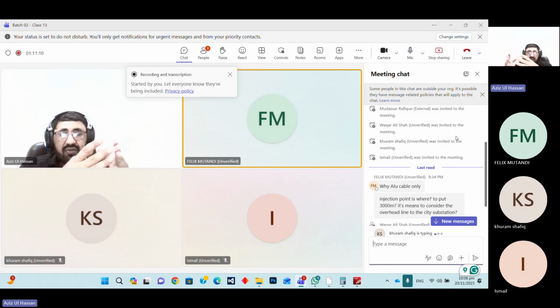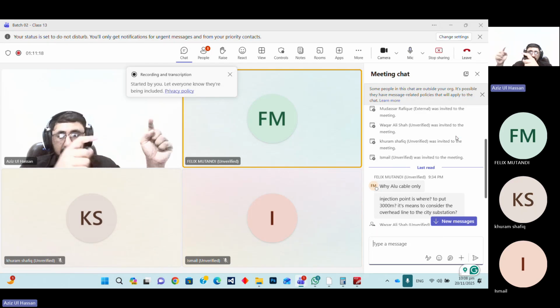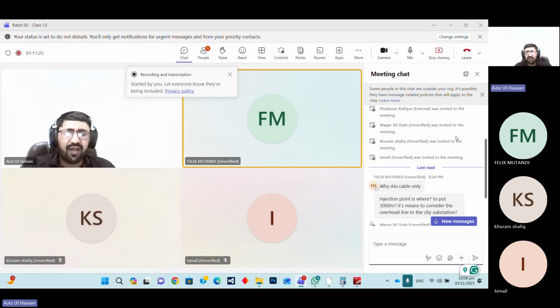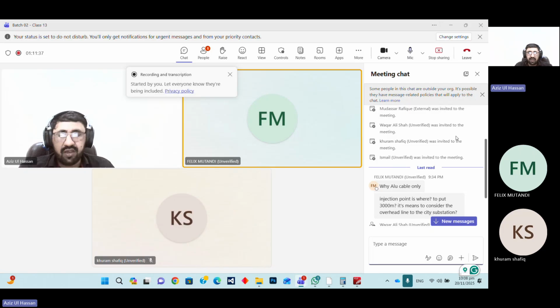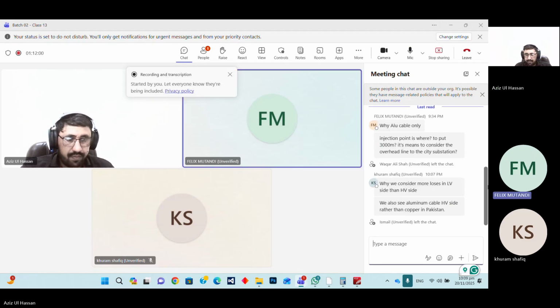But the MV stations are in your case mostly. The 3,000 meters which I put is for the overall power plant. The MV cable will be used, but I just put that value as an estimated value, not a correct one. We should use it as per your project and where the system is installed, where the MV cables will travel. So that is why it's just an estimated value, not an exact value. But I can tell you that our voltage loss is in between those values. Okay. For example, if you can write that in the reports from PVsyst reports, it's possible.